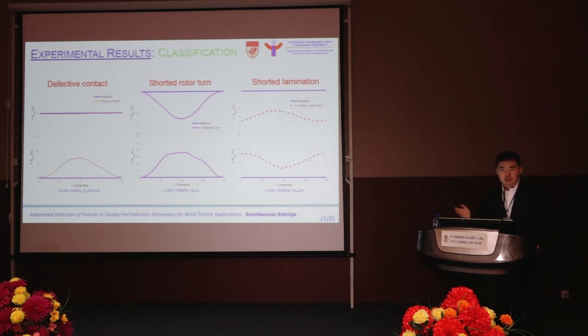for these faults, like rotor turn fault and also stator core fault, those faults are really hard to detect, because the online monitoring now in the field is based on the frequency taken by the measuring instruments when the wind turbine is operating, which has a lot of noise. Because of that noise and also the low frequency in the rotor circuit, the faults are very hard to detect.